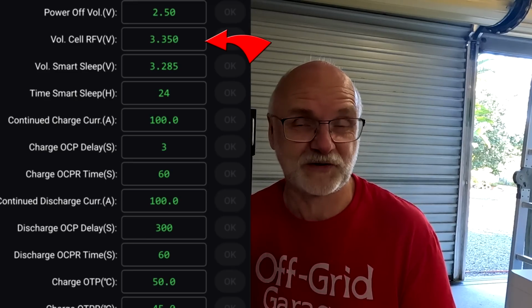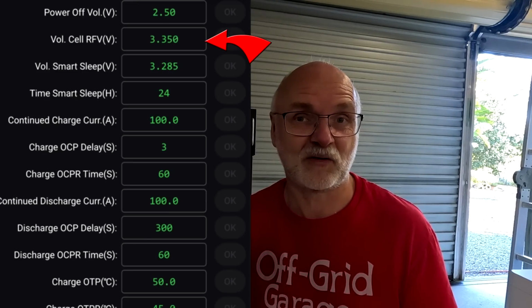There's nothing. The idea here is to get rid of this parameter in the settings and instead use the float voltage parameter to trigger the BMS to 100%. That means we can reach 3.45 volts, for example, go into absorption voltage, let the balancer do its work, and once the timer set in the BMS runs out, it goes into float, which is a lower voltage setting. Once this is done, we've fully absorbed the battery at 3.45 volts, and the battery is 99.9% charged. So this only requires a software change to make it work.